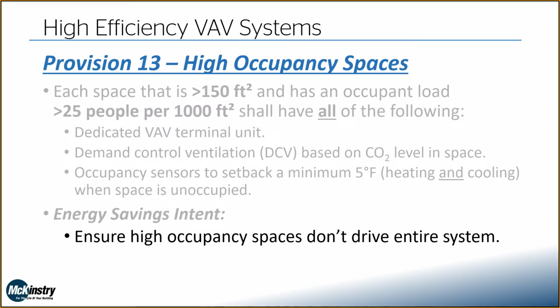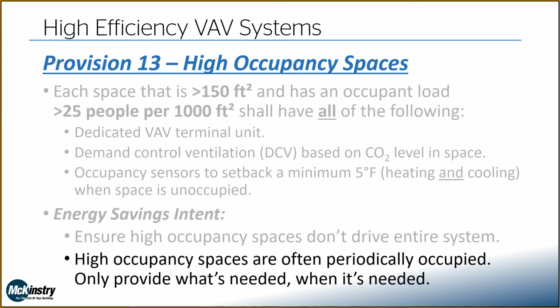The idea here: make sure those high occupancy spaces aren't driving the entire system, and that's kind of a recurring theme where we don't want one or two spaces driving our reset strategies. And often these high occupancy spaces are periodically occupied. So what we design it for is really not what it's going to need 90% of the time. So let's only provide what's needed when it's needed.